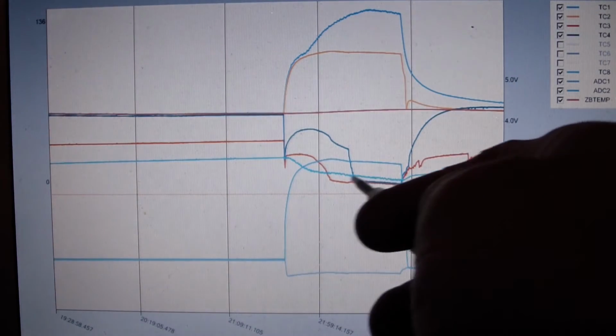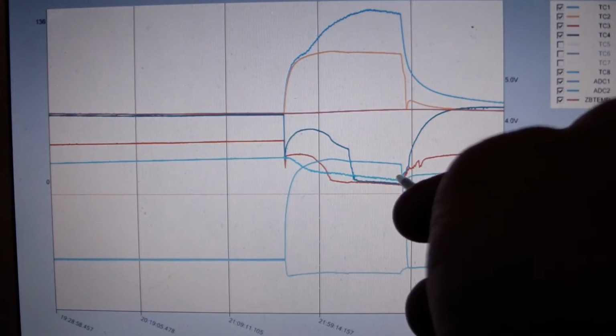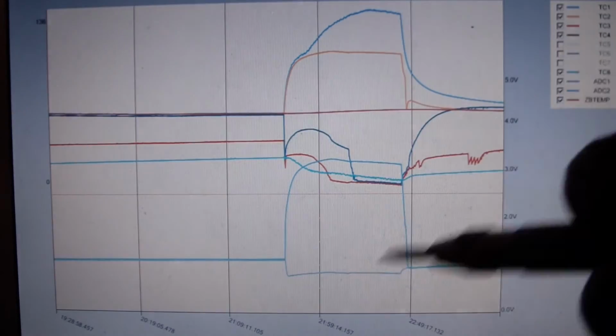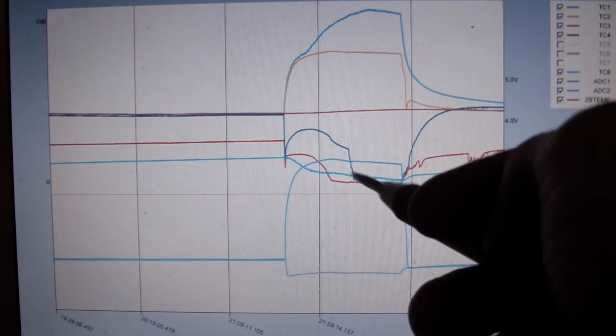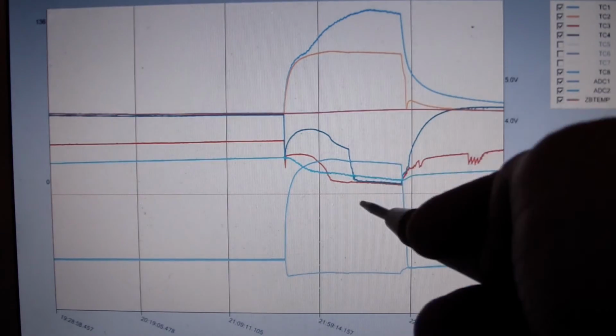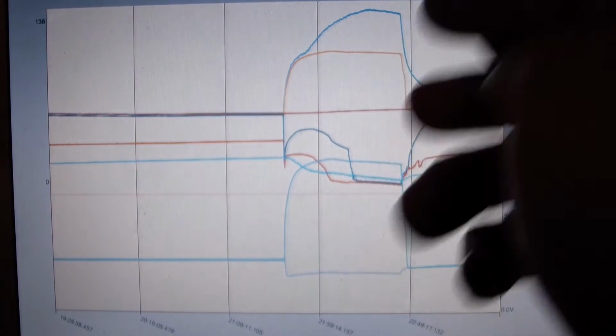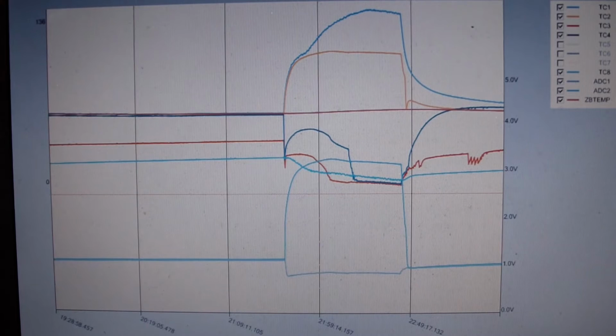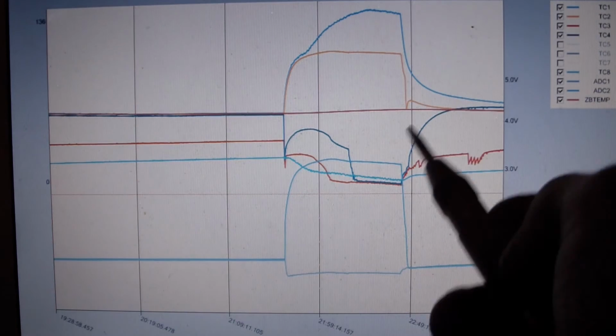Once we finally reach close to saturation on the suction line, we're getting better mass flow rate through the compressor. We're getting better mass flow rate through the capillary tube. Everything's running pretty swimmingly. We'll just get a drop in the discharge superheat up there. It slowly falls off a little bit, and I think that has a lot to do with the fact that the compressor is getting better cooling from the suction line.